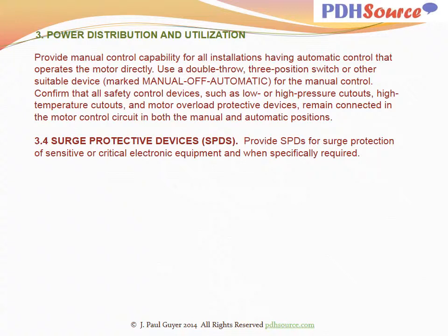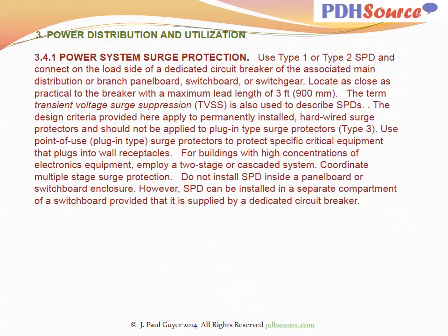Provide surge protective devices for surge protection of sensitive or critical electronic equipment and when specifically required. Use Type 1 or Type 2 SPD and connect on the load side of a dedicated circuit breaker of the associated main distribution or branch panel board, switchboard, or switchgear. Locate as close as practical to the breaker with a maximum lead length of 3 feet. The term transient voltage surge suppression, TVSS, is also used to describe SPDs.